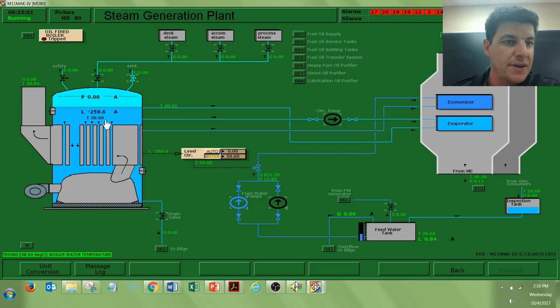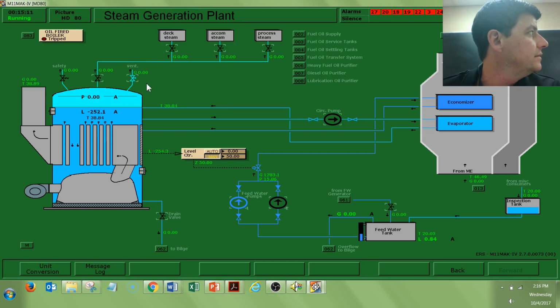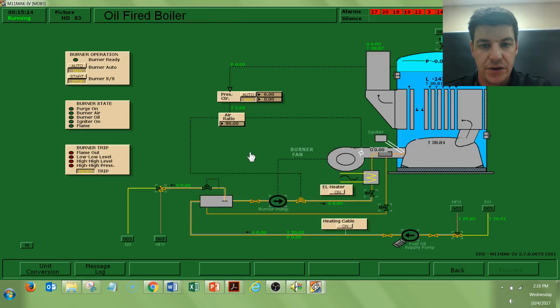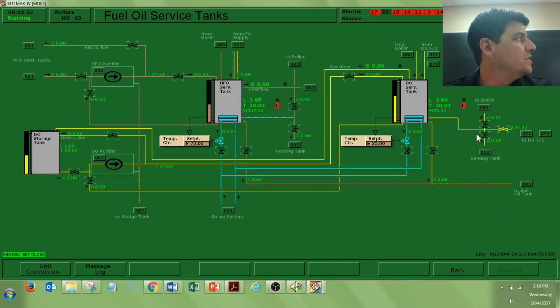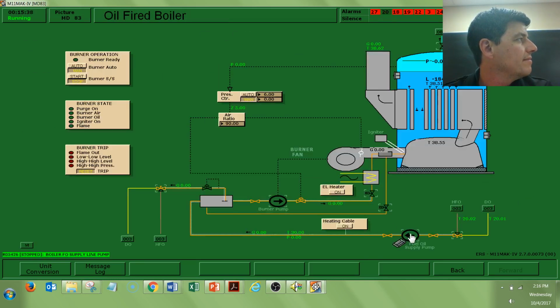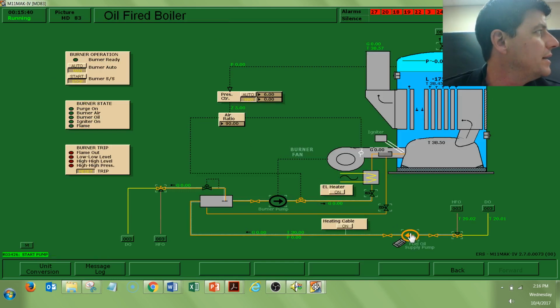While I'm waiting for all that to happen, I can verify that my vent is open. And let's go start the preparations for lighting the boiler. In order to light the boiler, I want to be pressure control in manual at 0 or minimum firing. I've got a pathway for diesel oil. Set my other valve so that it recirculates back to the diesel oil tank. I'll need to open up a pathway to the boiler. Turn on my fuel oil supply pump and verify I do have some flow.